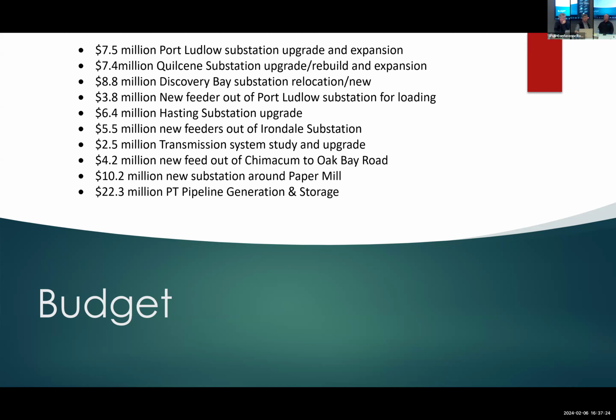Well, Ludlow substation isn't end of life, it's too small. So we're going to leave the existing bay there and put a second bay in. The theory behind it: most of the time, if this transformer fails, I can transfer all the load over to the other transformer. The only time I wouldn't be able to is during our coldest time of year. But because it'll have 2 transformers, it allows other adjoining substations to carry less load, and during an outage on the coldest day of the year, we could do some switching.